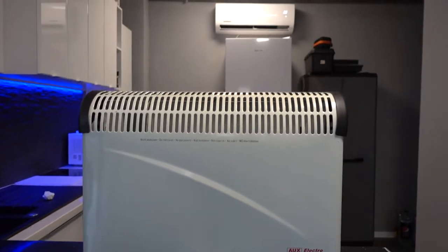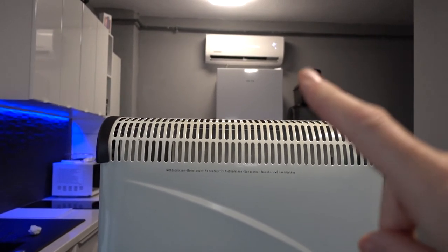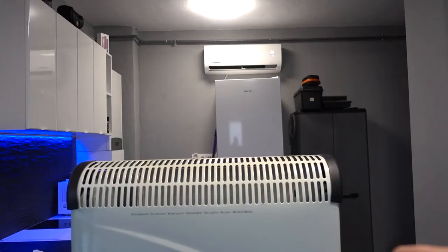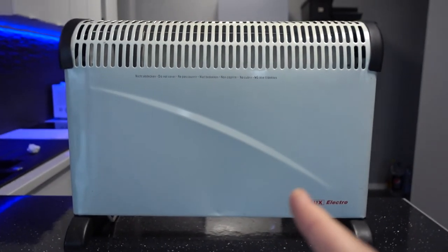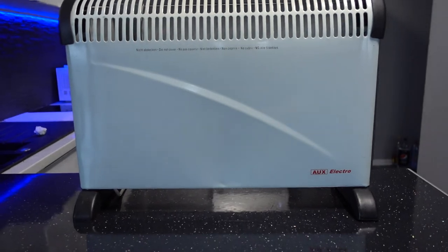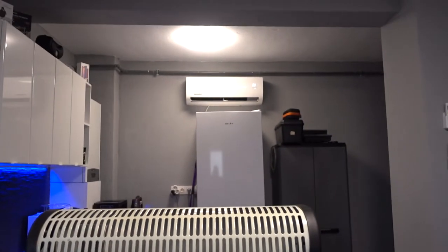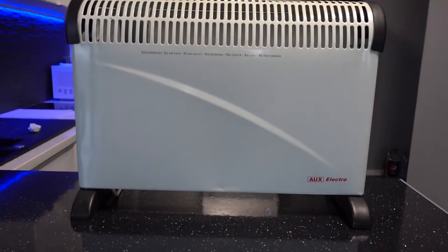To make it simple: if you have to choose between the two, all the way down to minus 10 degrees Celsius the heat pump is going to work really well. The cooler it gets outside, the more it's going to cycle off to defrost itself. The resistive heater is going to become more relevant if temperatures drop under minus 10 degrees, but the heat pump uses a lot less power over time compared to that heater.